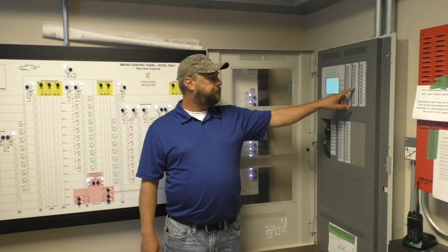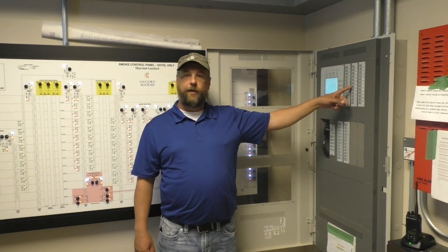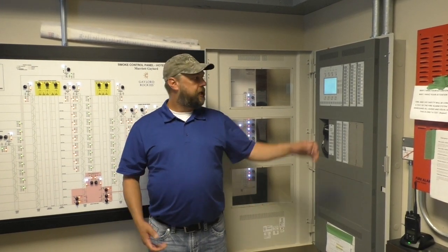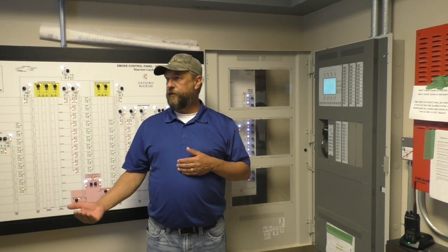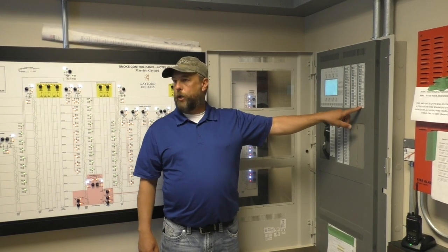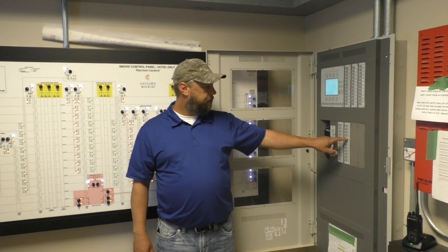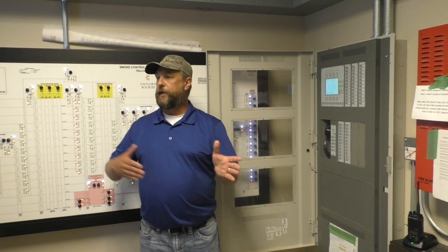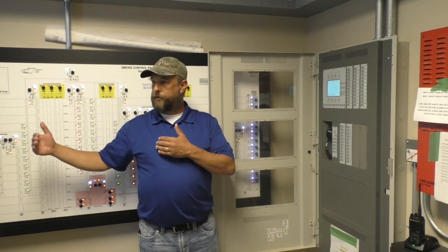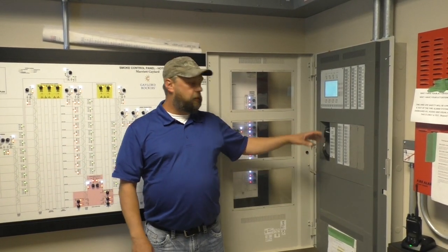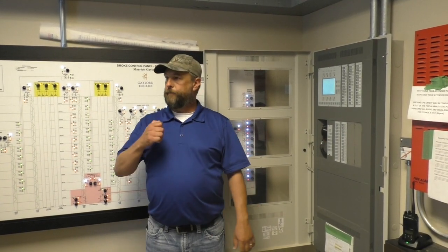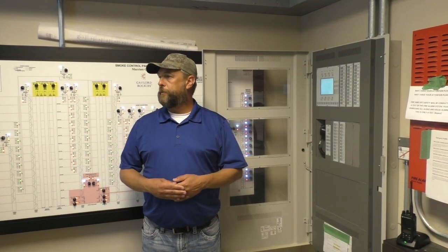The floor paging: you push floor page, the LED comes on, pick up that mic, key into it, and then you can speak your message, and it's only going to speak over that specific floor. If you wanted to isolate hotel versus convention center, it has a hotel all call and a convention center all call. That means you're speaking through every speaker on every floor, every common area, per hotel or per convention site. If you want to speak throughout the entire complex, you have an all call button right next to the mic. Pick up the mic, key into it, and now you can speak your message.